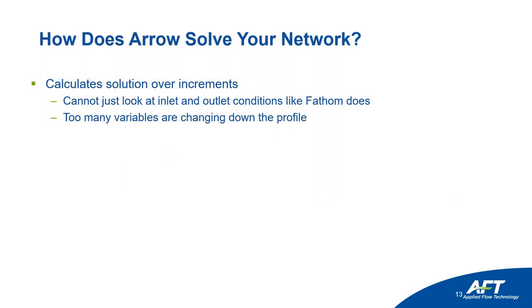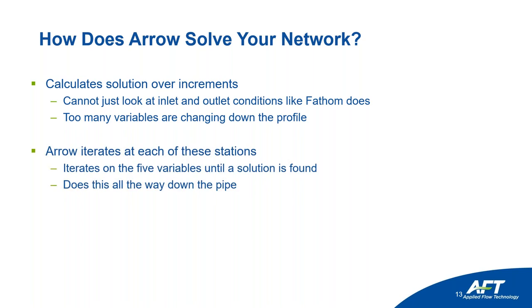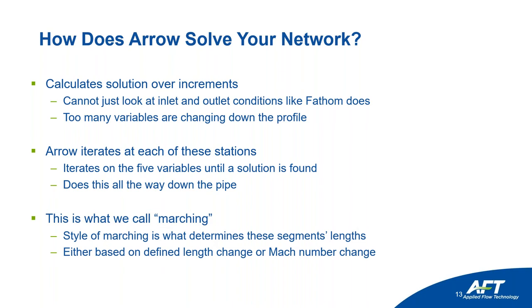Let's talk about how Arrow solves your network. We have to solve those differential equations, but it does so numerically — in distinct and discrete chunks. We can't just look at inlet and outlet conditions like Fathom does; there are too many variables changing down the profile. So Arrow iterates at each station throughout the pipe on those five variables: pressure, temperature, density, velocity, and enthalpy, all the way down the pipe. This is what we call marching.